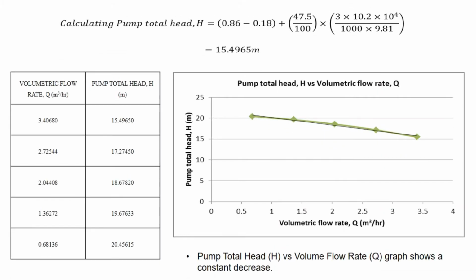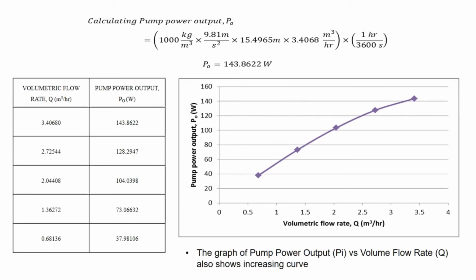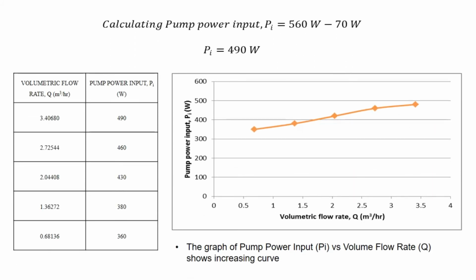Next, we need to calculate the pump total head by using the equation. The percentage of differential pressure is substituted into the equation to find the pump total head. And then, to calculate the pump power output, we need to substitute the volumetric flow rate into the equation to find the pump power output. And then, to calculate the pump power input, the power is minus by 70 watt to get the pump power input. As you can see from the table, as the volumetric flow rate decreases, the pump power input also decreases.